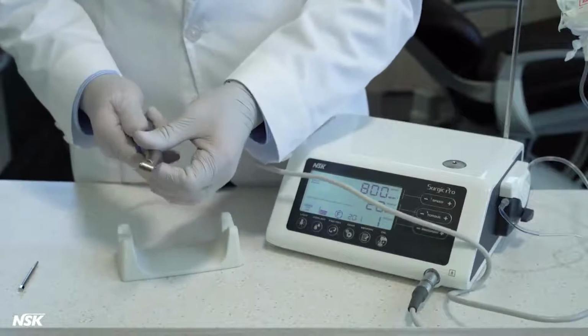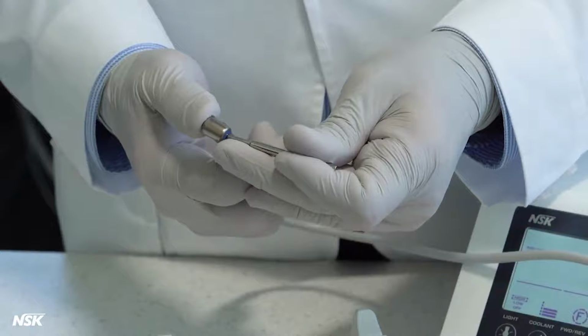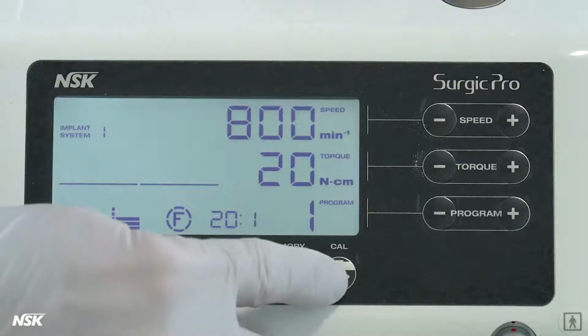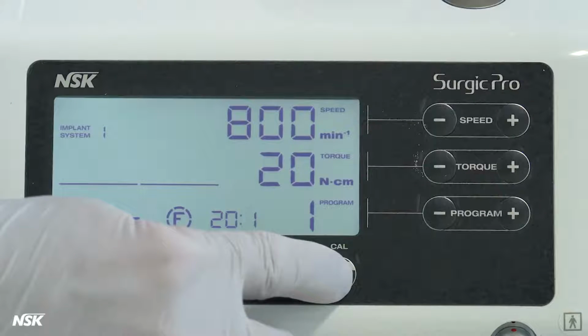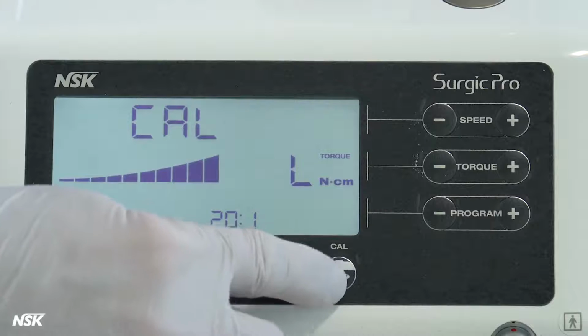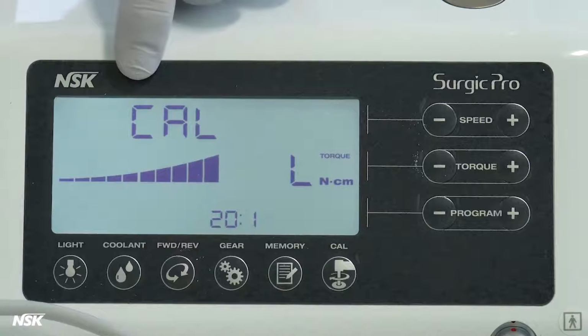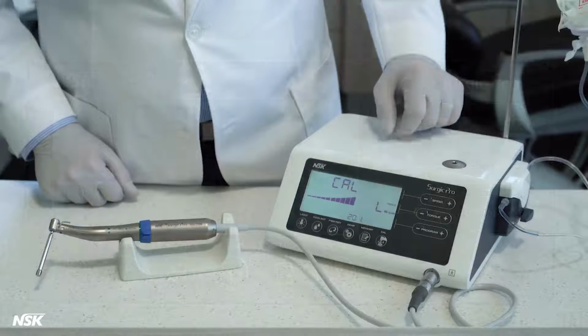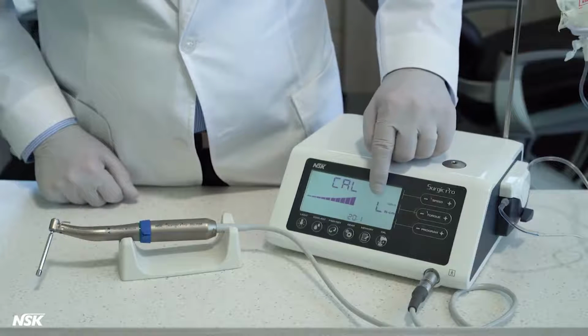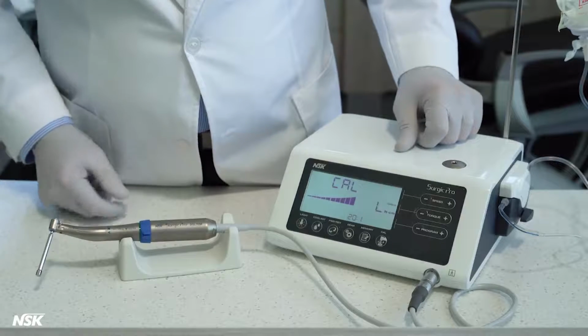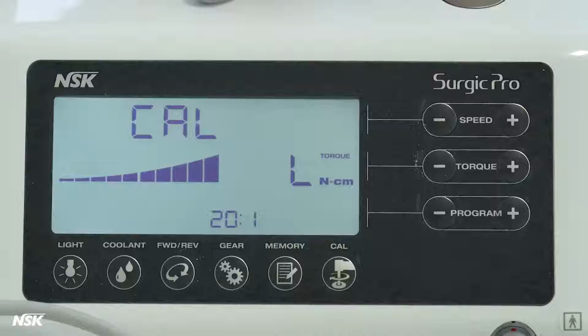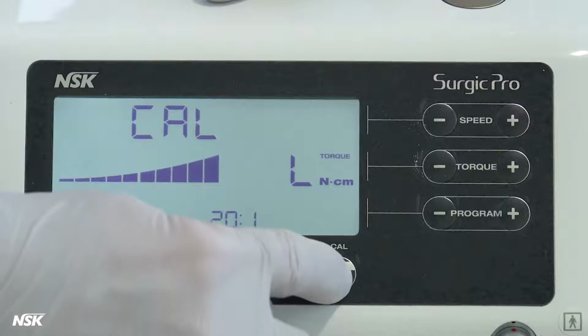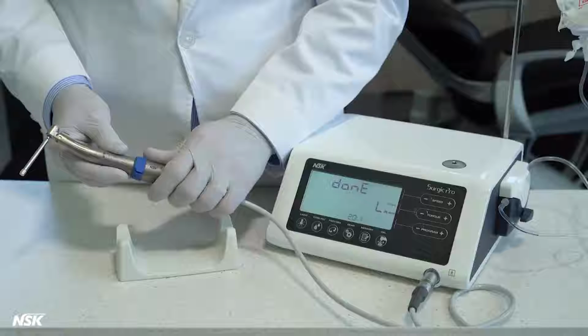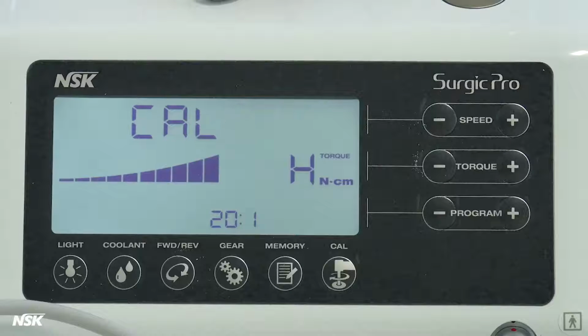Attach the 20:1 attachment to the motor and insert the calibration drill. Press the Cal key for 2 seconds. After you hear a long beep, the display will turn to calibration mode. You're ready to calibrate. Step 1 is no load calibration. Torque displays L. Hold the motor in one hand and press Cal key. The drill will begin to rotate. Once this part is completed, you will hear a beep and see Done on the display.